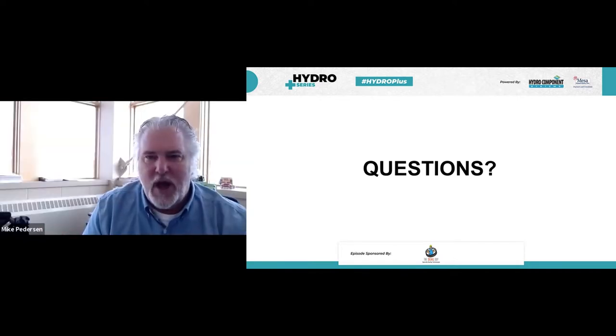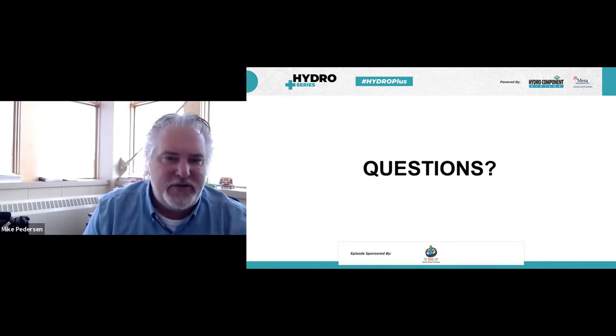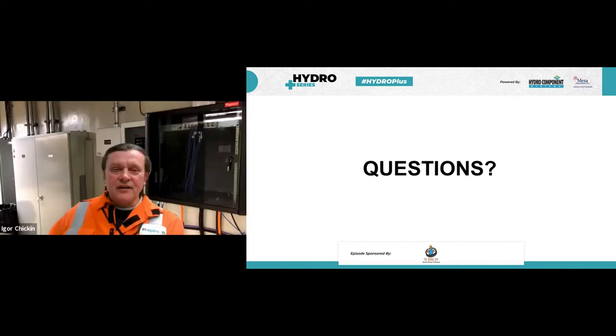Okay, good, thank you. Igor, question for you: do generators need online partial discharge monitoring systems? Definitely, it does help to look at the trends much more often. Not only when we go with the PDA-4, let's say with portable testing equipment, we take a reading at one particular condition. But when the operating condition changes, we are not able to. When we use a continuous online monitor, we can track the partial discharge activity over the whole range of operating conditions, which may really help us to determine the failure mechanism.